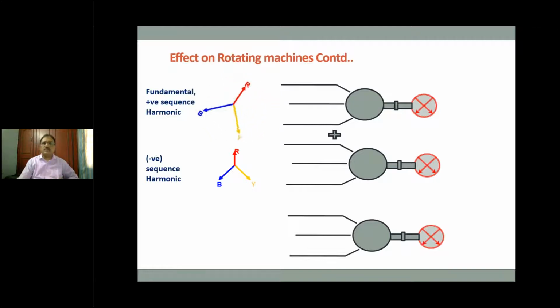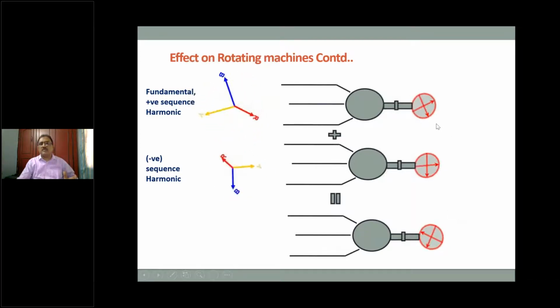The other way in which you will know the presence of harmonics is by looking at the positive and negative sequence. When you use a nonlinear VFD, the motor will have, apart from its own torque, additional torque added by the positive sequence and negative torque added by the negative sequence, which is the fifth order. 5, like I told you, 5 plus 6, 11, 11 plus 6, 17. Those numbers will be opposing the torque of the motor. So there will be a reduction in speed of the motor because of the opposition, and there is also a positive torque added. It will create a pulse effect in the motor shaft, and therefore the motor will be drawing more power in order to deliver the load.